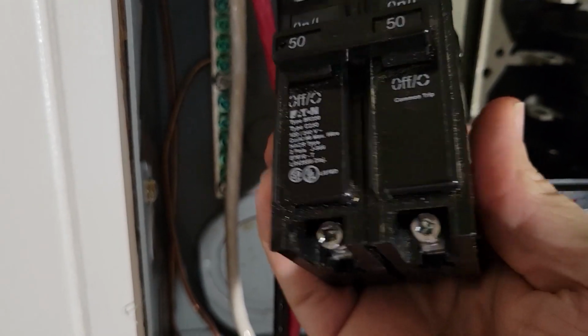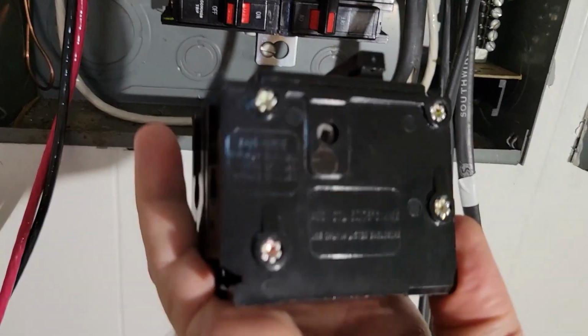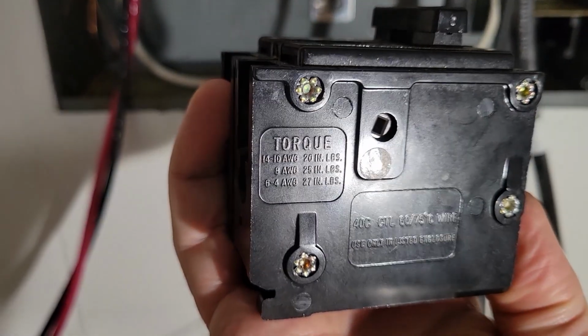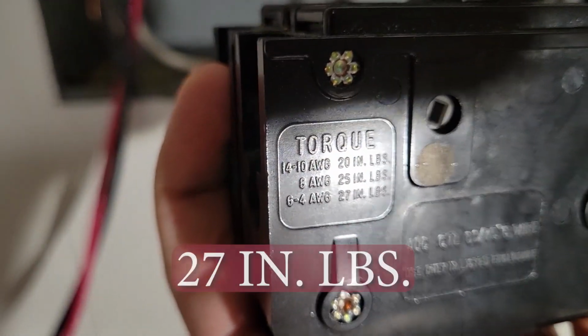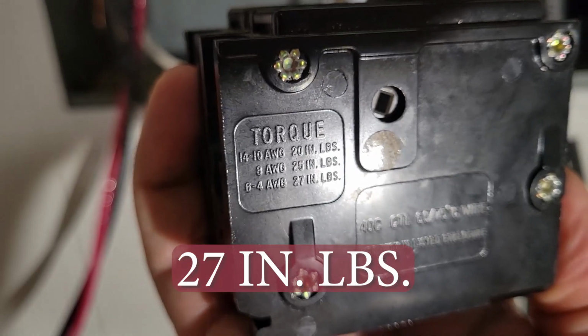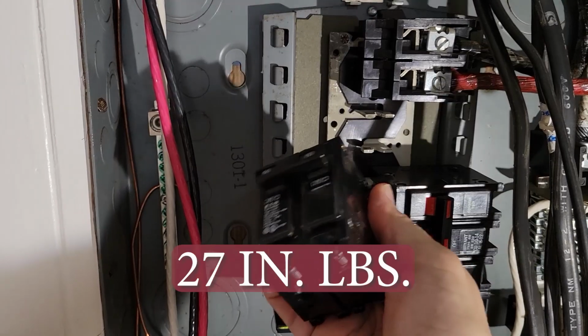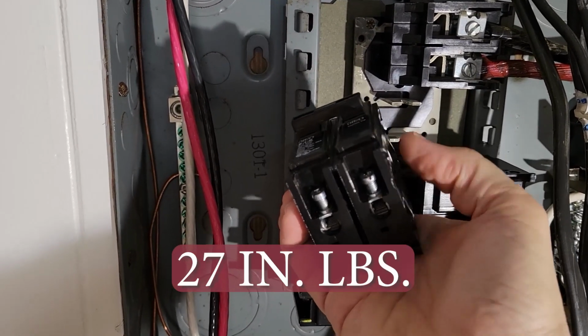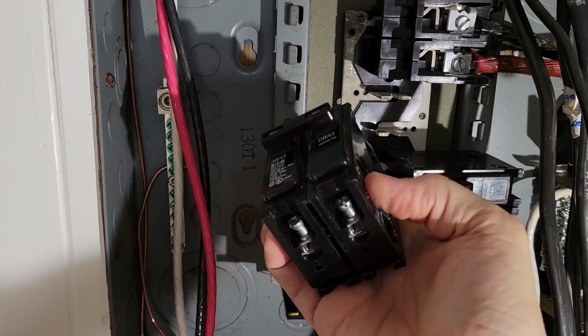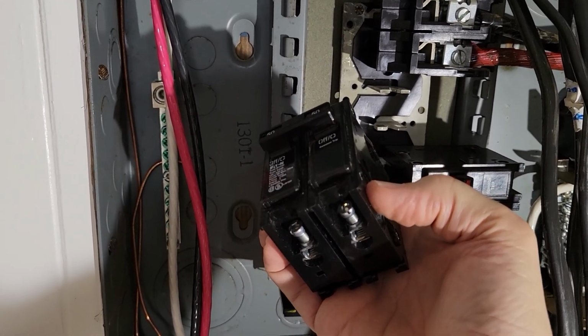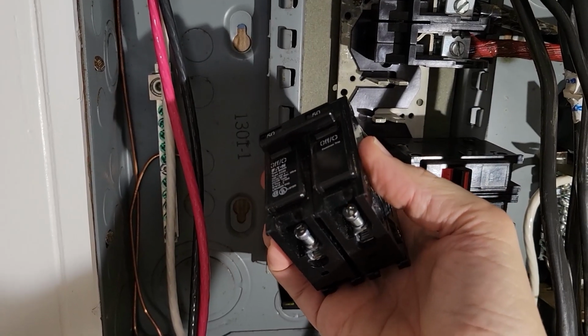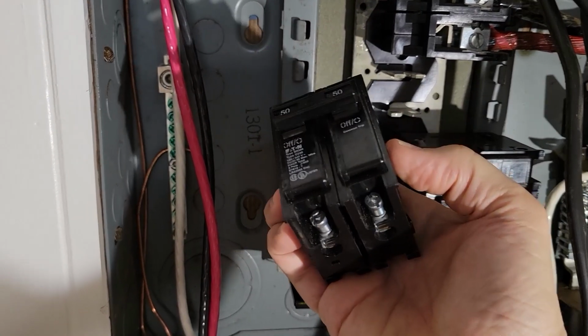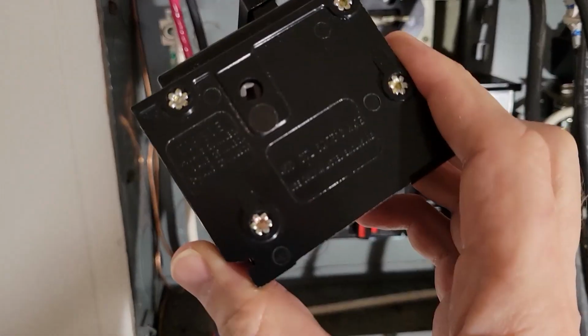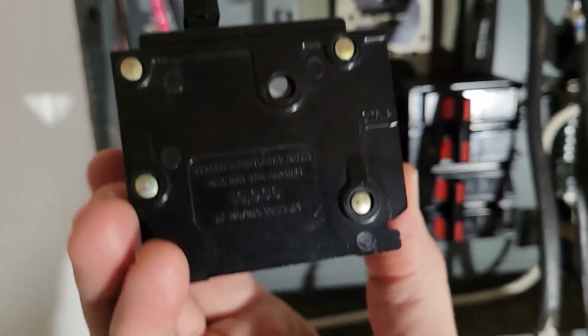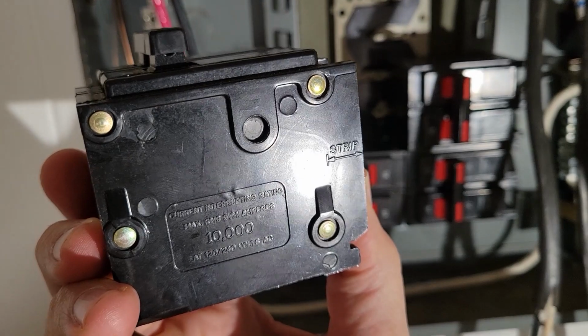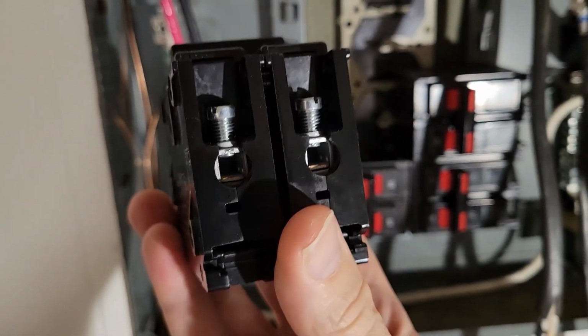But they do need to be torqued down, and that specification is usually on the side. Since we're using 6-3 wire, it's 6 gauge, so that gets 27 pounds of torque. The torque's important because you don't want these wires to loosen up after they heat up and cool down. They expand, they contract, and torquing assures that despite all that, they stay in place. Along with the torque specifications, there's usually a guide that tells you how much insulation you need to strip off so that you can make a clean connection.